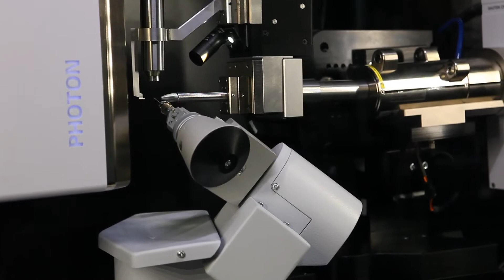On our top-of-the-line instrument, we can have a system with two sources, one molybdenum and one copper, both microsources, as well as the Photon 100, and none of these components require any cooling water.